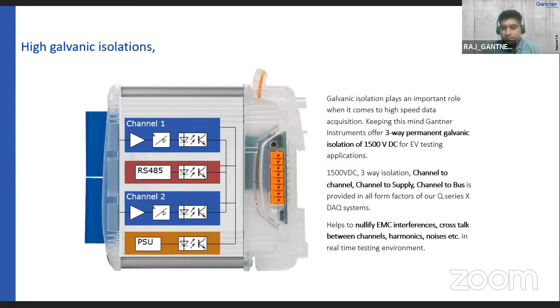So a complete 3-way isolation of 1500 volt DC for EV testing applications, because as you know, in an EV you are going to measure high voltages and high currents. So currents in the range of more than 1000 amps and voltages also in the range of 1000 volts. So you require a system which has a very high galvanic isolation. So we have gone with the maximum of 1500 volt DC, which will really help you to take all kinds of measurement in the EV testing environment.